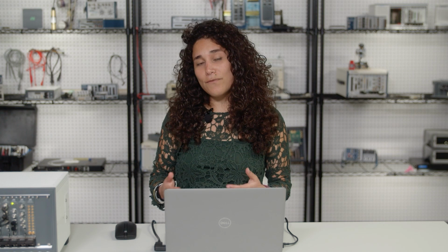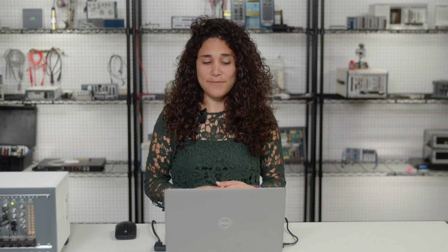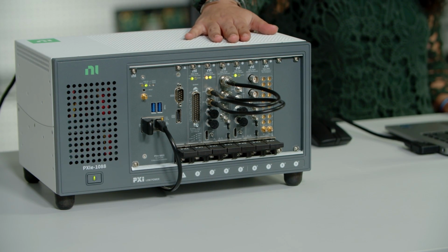Each channel of our waveform generation has its own engine, which allows each channel to use its independent triggers, generate different types of waveforms, be configured separately, and start and stop asynchronously.